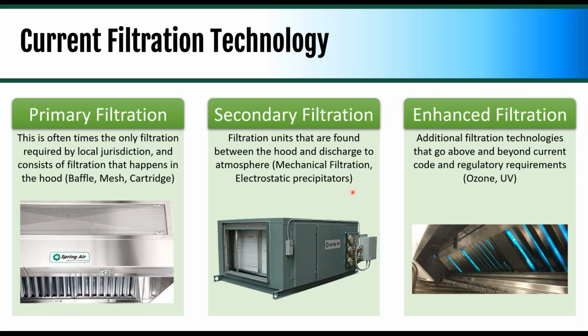The issue I have with these is that they lose their efficacy very quickly because as those particles are knocked out of the air, they land on that charged plate and reduce its ability to remove further particles out of the air. There are water wash systems in place for some units. They're also very heavy, but the efficacy thing is the thing that gets me hung up. Whereas the mechanical one, that filter is going to load and load and load. And as it's fully loaded, it's not going to be able to pull air through. And so that's where those filters have to be replaced in order for that unit to function properly. Again, we've got safeties built in and things like that, but I will tell you there's a way around everything. However, people would have to get really talented at rigging ours to be able to run without filters at this point.